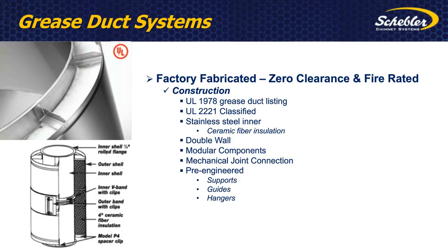Now, factory fabricated products will be considered zero clearance and fire-rated. You would need to utilize a UL 1978 listing, which gives a product a grease duct listing, and UL 2221 classification, which is where the fire rating testing is done. These products are almost exclusively constructed of stainless steel inner liners, ceramic fiber insulation, and then an outer shell, which can usually be stainless steel or maybe aluminized steel. These products are modular components and have a mechanical joint connection, which wouldn't require any field welding. Now, a UL listed product is also going to include supports, guides, hangers. So it's a system that's gone through testing of all the structural components. So you really have a pre-engineered system.